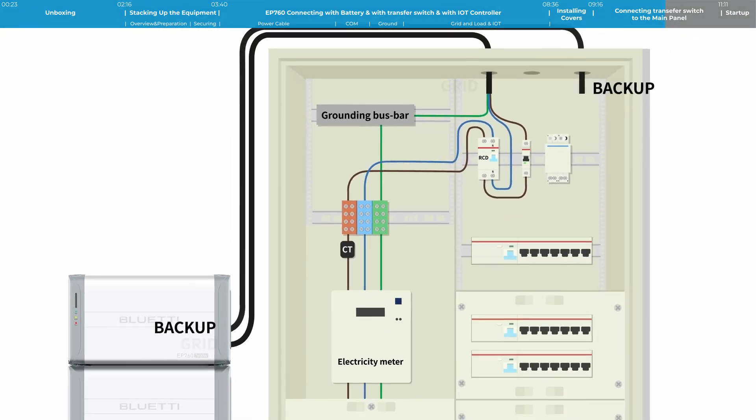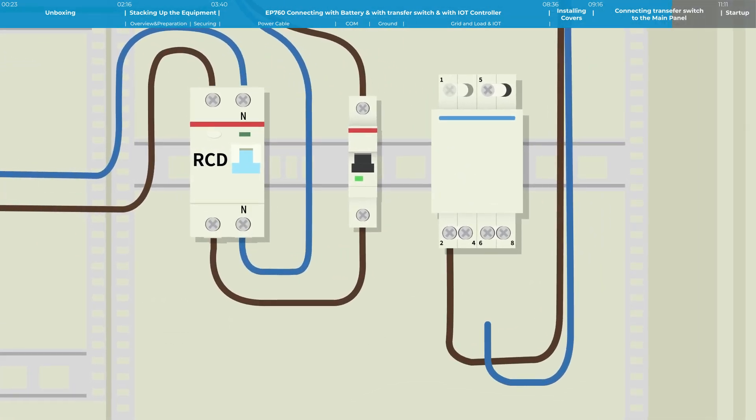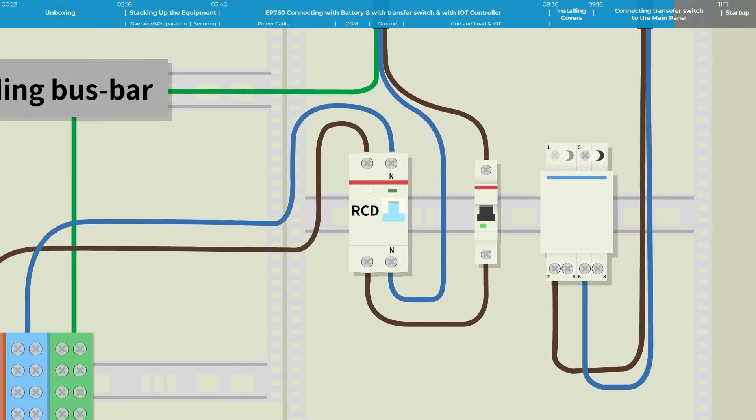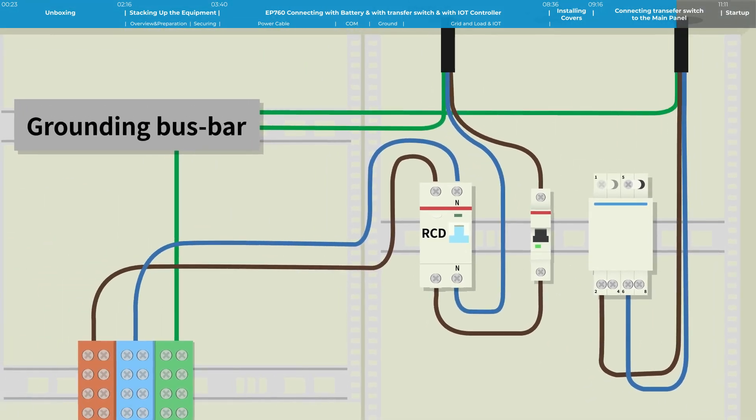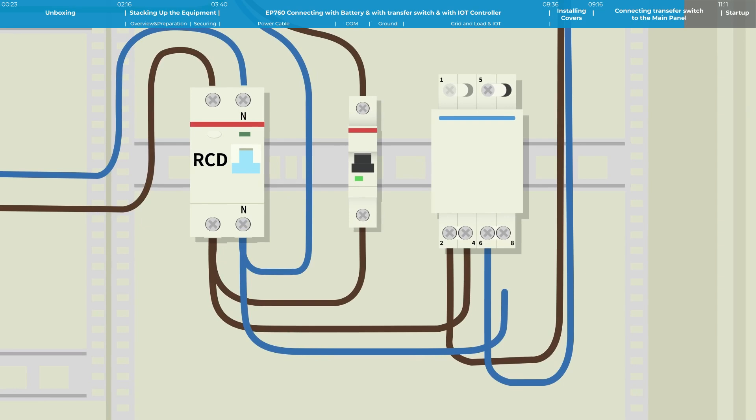Connect the EP760's BACKUP cable to the 2P transfer switch terminals: L to pin 2, N to pin 6. Connect the PE cable to the PE bus bar. Then connect one live wire and one neutral wire from the 2P RCD terminal to the 4-8-N terminal of the 2P transfer switch: L to pin 4, N to pin 8.